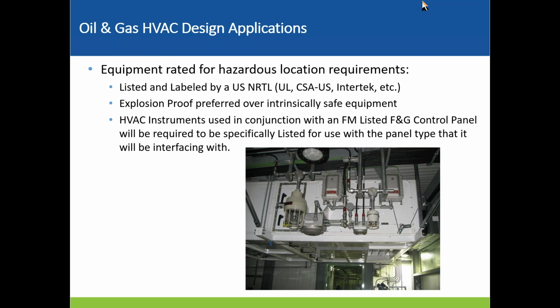Explosion proof is generally preferred over intrinsically safe equipment. I say this because I've done some intrinsically safe work, and there are a lot of requirements that go into it with the wiring, tagging, and coloring, and most people don't know how to build them correctly. It becomes a problem once your QA inspectors go down there and start pointing out all the problems. I think I had about a $30,000 refund at one point because it's that hard for them to build it that way.